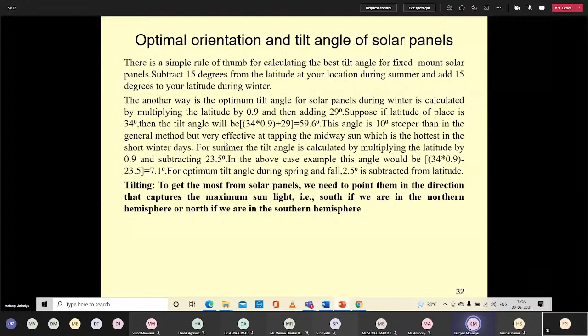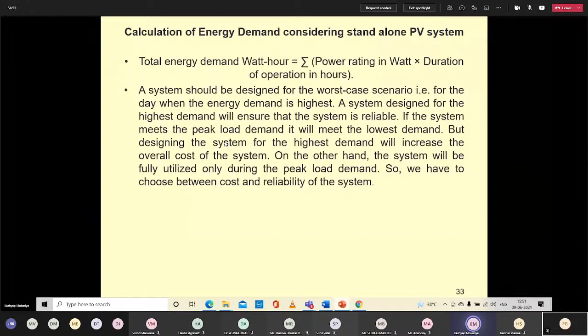Now the calculation of energy demand considering a standalone PV system. Total energy demand is equal to the summation of power rating in watts into duration of operation in hours. A system should be designed for the worst case scenario. For example, for the day when the energy demand is highest, a system designed for the highest demand will ensure that the system is reliable. If the system meets the peak load demand, it will meet the lowest demand. But designing the system for the highest demand will increase the overall cost of the system. So you have to choose in between where you go for the energy demand assumption.